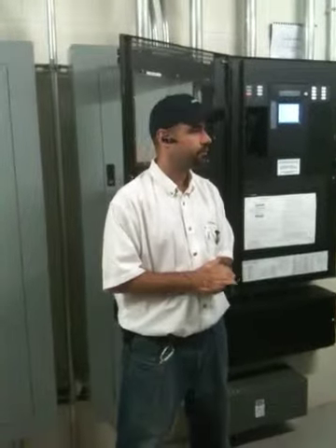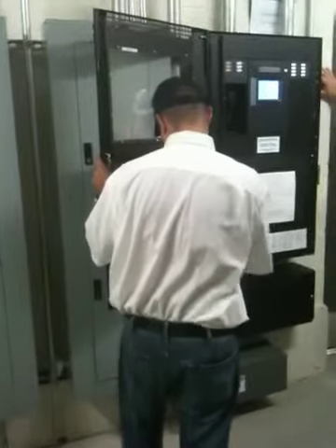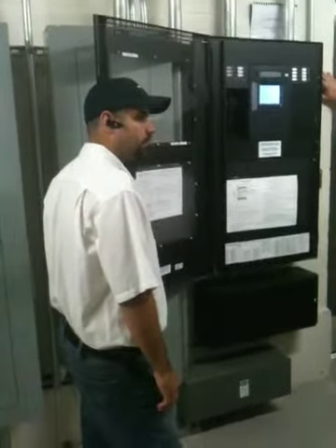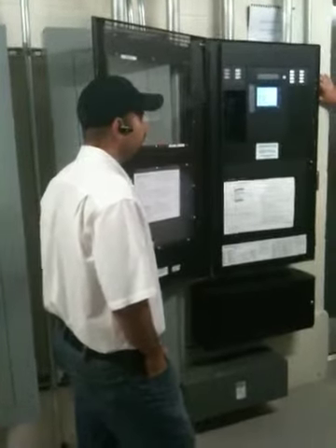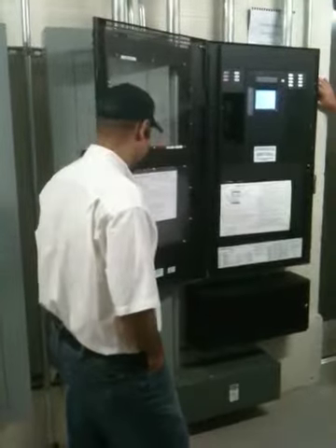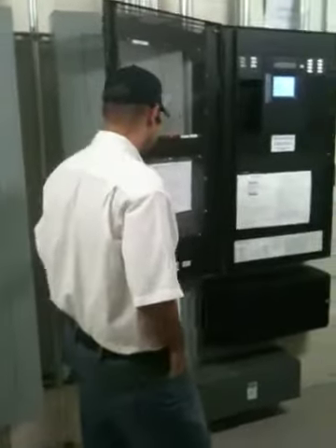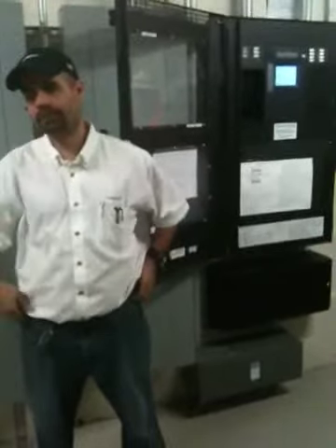Total smoke detectors? 18 and 25 beats. Does it have an interface board for a portable printer, or a sensitivity report? No, it doesn't. We can do a sensitivity report on the screen, but we can't print it out. But there's not that many smokes, so it's a short list. Yeah, it's fine. It shouldn't be that bad to look through. Are the annunciator panels in the front over here? There's one in the front entrance, and there's one right in front of the sprinkler room.